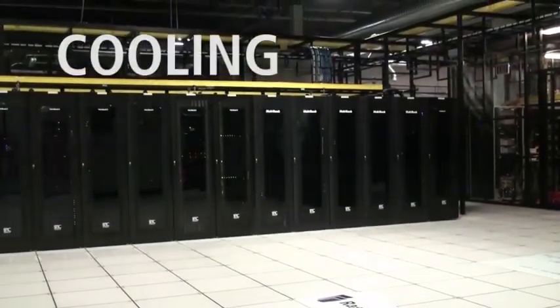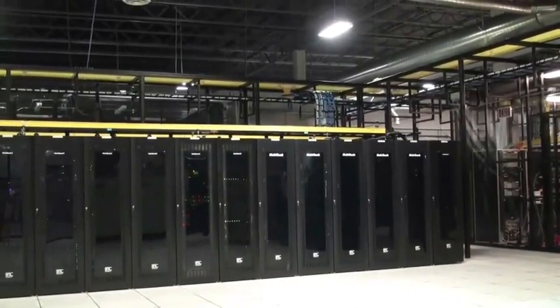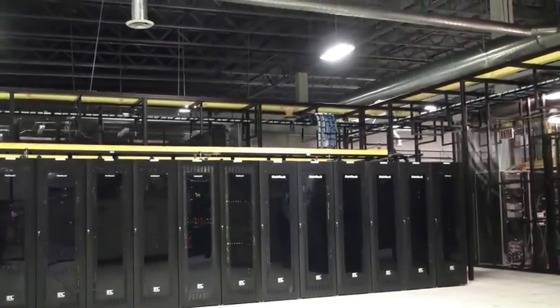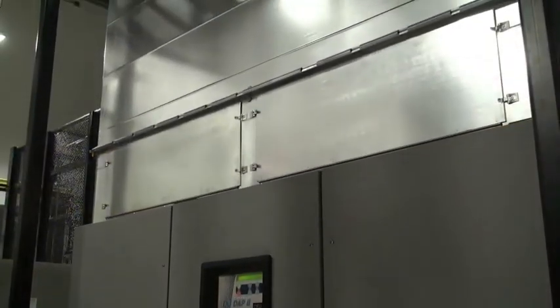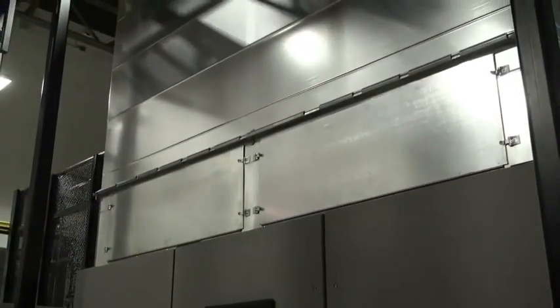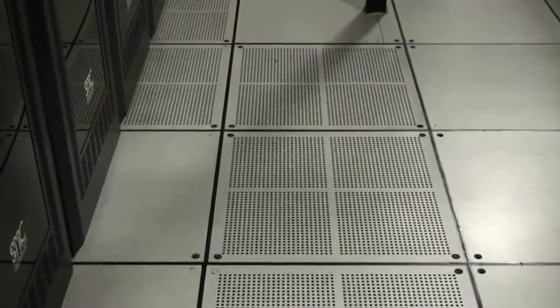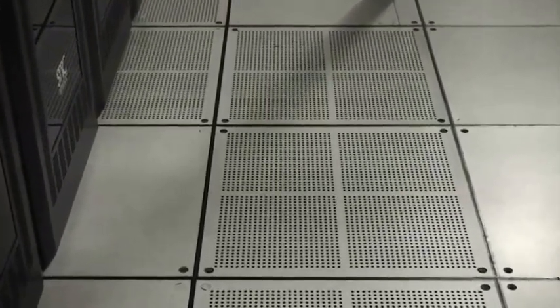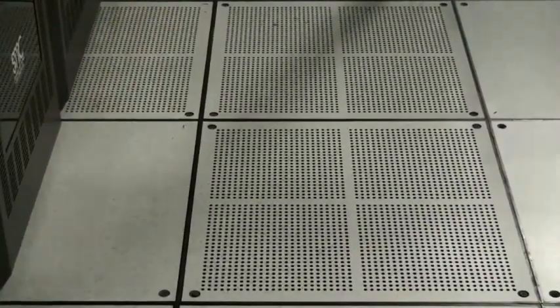Everywhere on the data center floor, computing gear is arranged into hot and cold aisles. Hot air is released into the ample overhead space afforded by the unusually high ceilings. The hot air is pulled into AC units throughout the computer rooms, where it is cooled by chilled water and released below the floor. Raised floors 3 feet high in phases 1 and 2 and 4 feet in the newer phases allow for a significant volume of cool air to be delivered back to cold aisles via perforated floor tiles.